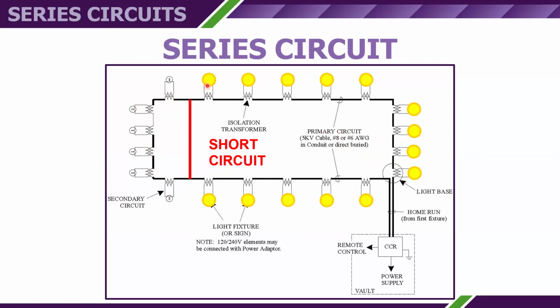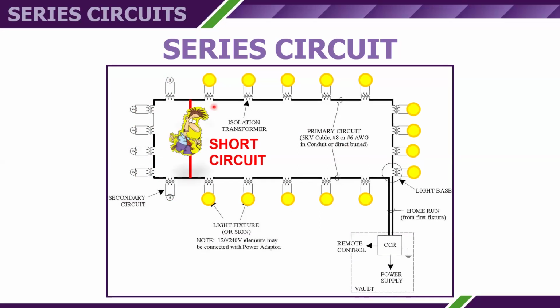Again, the problem is going to be between the last two fixtures that are operating properly. And again, we want to make sure that we do not become part of the Airfield lighting series circuit. It takes 1/10 of an amp through a vital organ to kill us, basically 100 milliamps. And our nominal output current on a constant current regulator, 6.6 amps, is more than enough to be fatal.